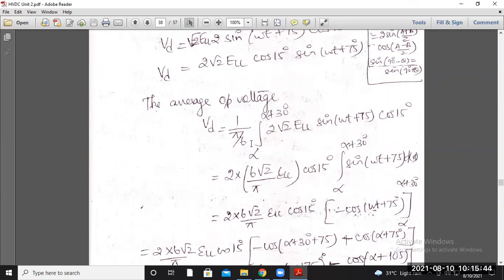When your second 6-pulse converter is delayed by 30 degrees in firing angle, you get the angle difference from alpha to alpha plus 30 degrees. Taking alpha equal to 0 degrees as reference, the second converter, the star-delta bridge converter, is advancing or delaying by 30 degrees. That's why we take alpha plus 30 degrees.